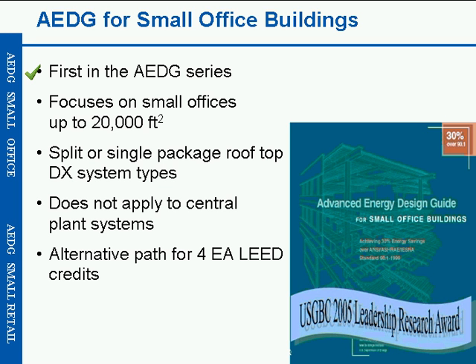So the first guide that was done was the Advanced Energy Design Guide for small office buildings. It really focuses on office buildings up to 20,000 square feet. And a typical system for these types of buildings across the country, as Shanti just mentioned, was a split or single rooftop DX system. The guide does not apply to central plant systems. We will talk more about this, but these guides are also tied into the LEED rating system from the U.S. Green Building Council, and it is an alternative path to get 4 energy and atmosphere credits.